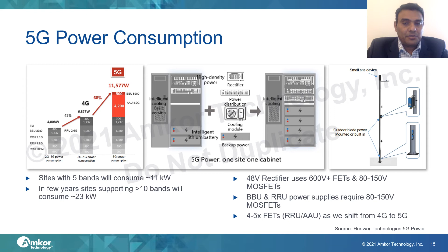According to telecom operators, the power consumption of a single band in 5G can be nearly 3 to 4x that of 4G with a similar configuration. A 5G baseband unit consumes about 300 watt, while a remote radio head consumes about 900 watt at only 30% load. As more frequency bands are added in the next 3 years, peak power consumption will increase to about 14 kilowatt, and beyond that, with the addition of millimeter wave, peak power may increase up to 20 kilowatt.